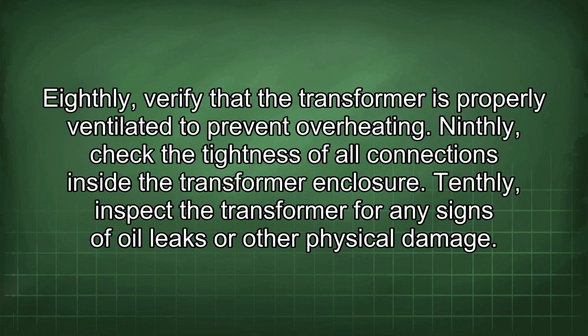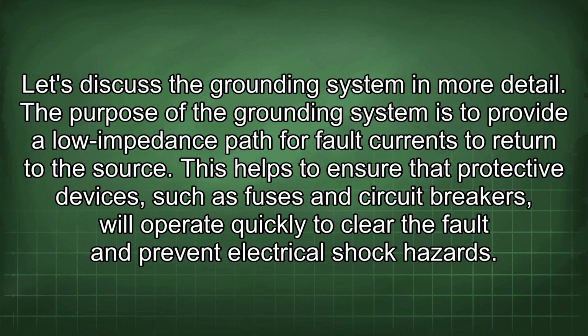Eighthly, verify that the transformer is properly ventilated to prevent overheating. Ninthly, check the tightness of all connections inside the transformer enclosure. Tenthly, inspect the transformer for any signs of oil leaks or other physical damage. Let's discuss the grounding system in more detail.